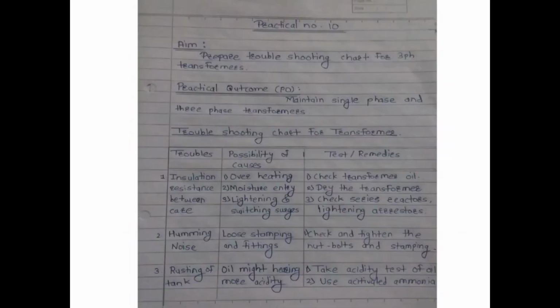Then practical number 10: the aim is to prepare a troubleshooting chart for a 3-phase transformer. So the practical outcome is to maintain single-phase and 3-phase transformers. The troubleshooting chart for a transformer has boxes: first the troubles, then the possible causes, then third the tests and remedies. First is insulation resistance between core; possible causes are overheating, moisture entry, lightning and switching surges.